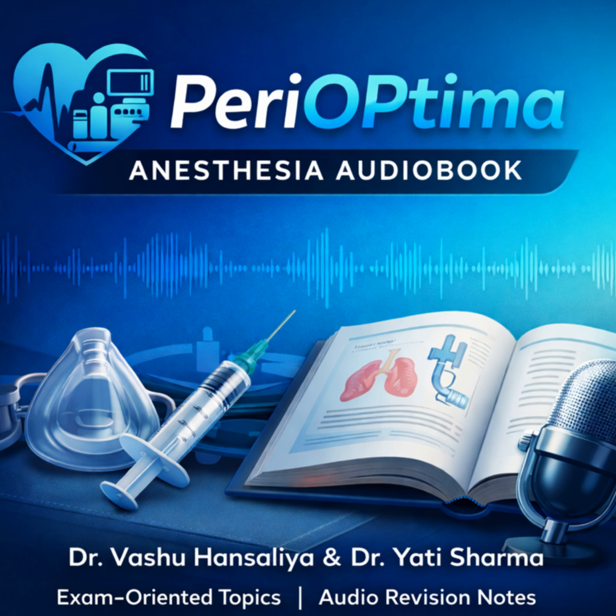Okay, let's talk about the Flowmeters. The outline marks this as absolutely essential. I take it this is a big topic. The Flowmeter assembly is the heart of the machine's accuracy. We use what's called a Thorpe tube design. The principle is a variable orifice, constant pressure system. I remember struggling with the physics of this in class. Is the flow through it laminar or turbulent?